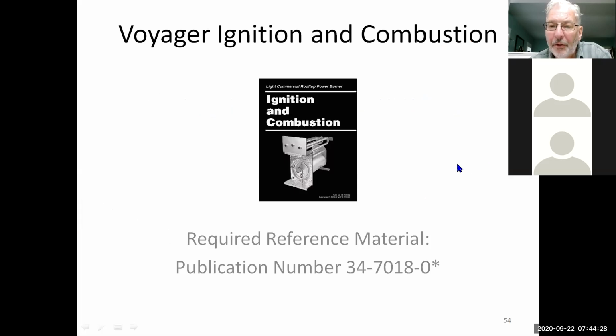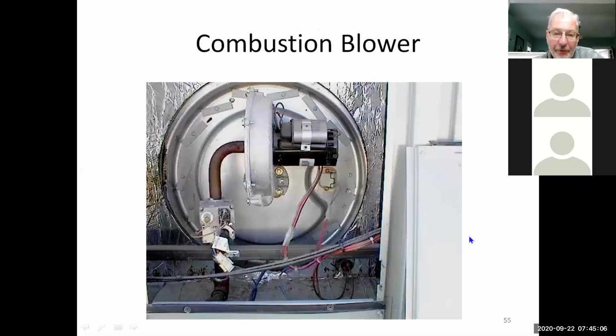So next one we're going to talk about is Voyager. Voyager is a little different. If you haven't worked on them, this heat exchanger design has been around since the 90s. On our models, the 3 through 25 ton, they set up pretty much identical. If you get into a bigger unit, some of the units actually have 2 heat exchangers in them. So if you get into the 30, 40, 50 ton units, this stuff will apply to it. It's just you're going to have double systems and double heat exchangers on some of the bigger equipment. But it basically works the same as the smaller equipment does too.